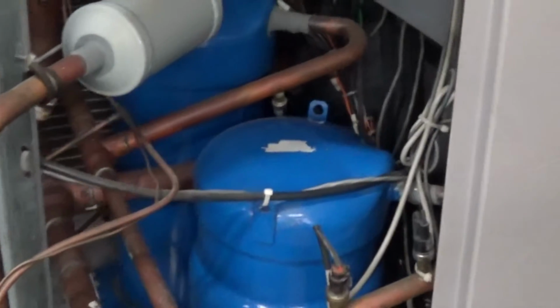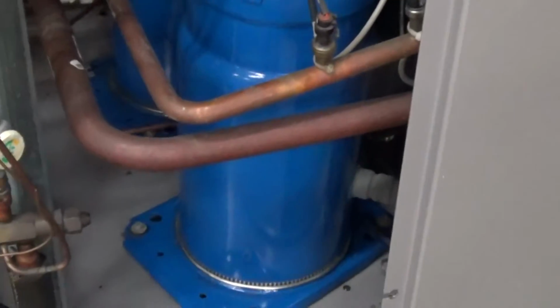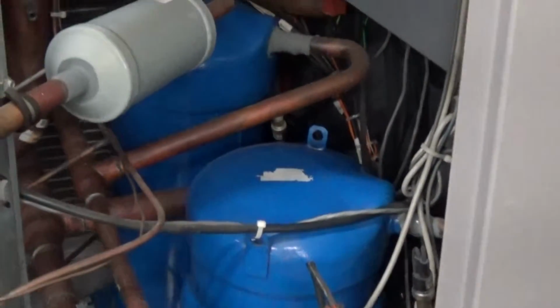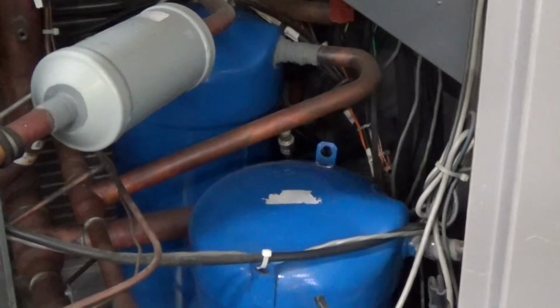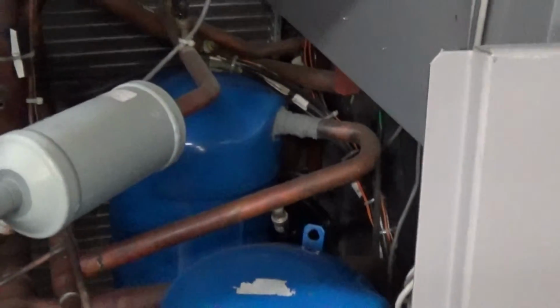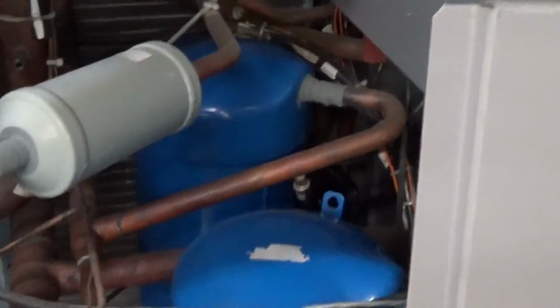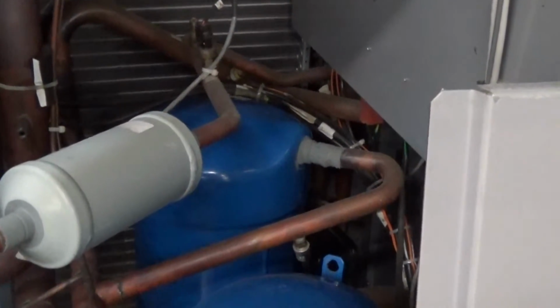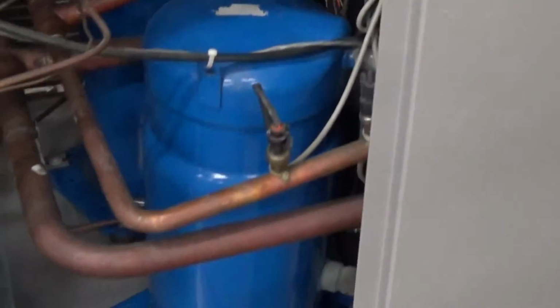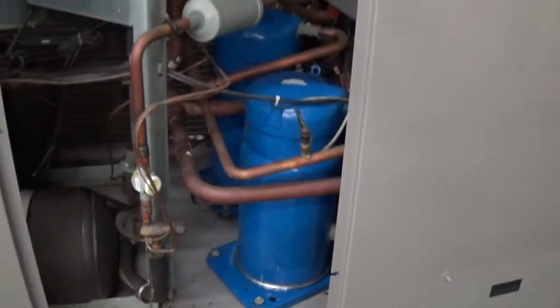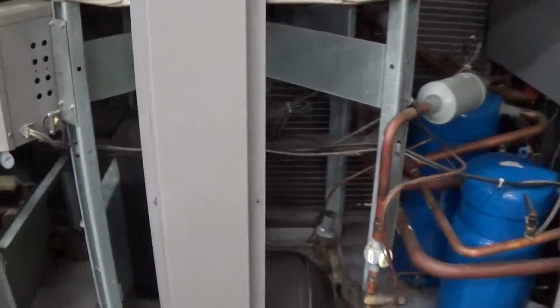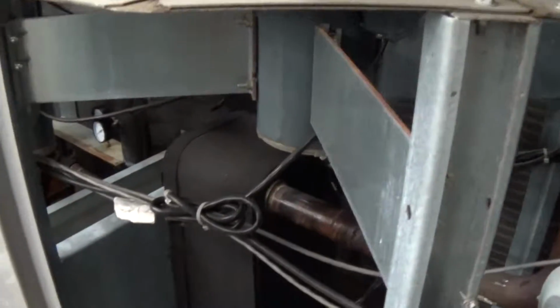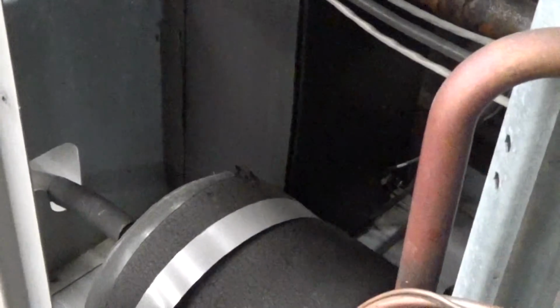This is a dual compressor system. These are the original compressors in the unit, which is nice. We want to see that because there have not been any problems with the unit in the past. One is slightly bigger than the other. That bigger one in the back, compressor 2, is about 13 horsepower. This one's about 9 horsepower. Scroll. Here we have our insulated brazed plate exchanger.